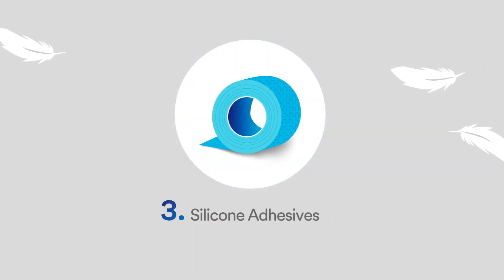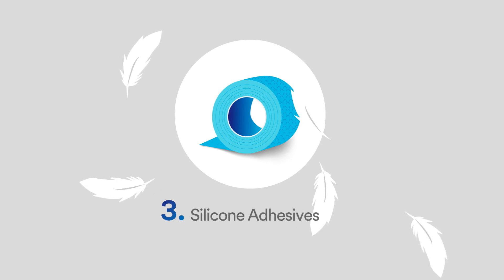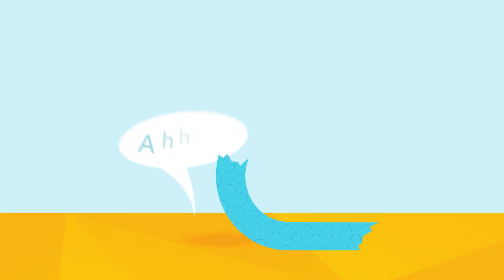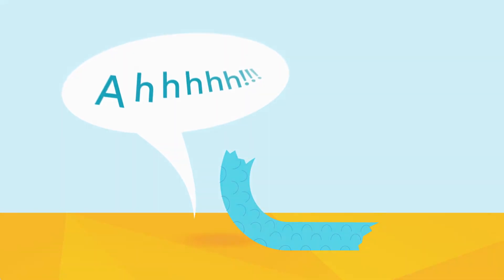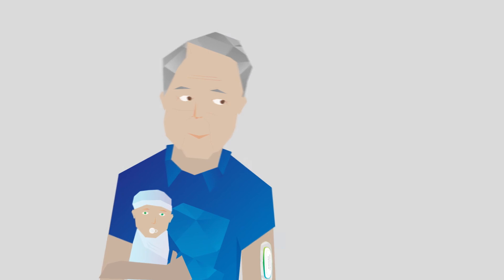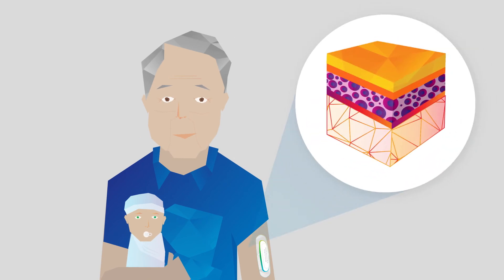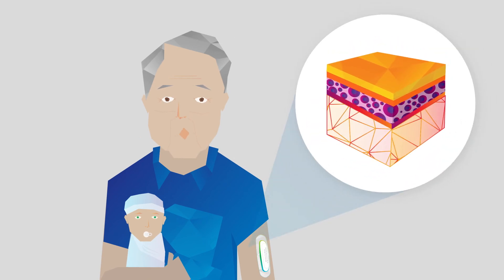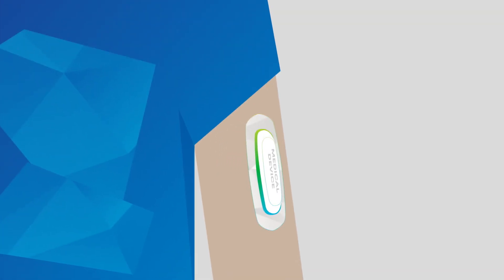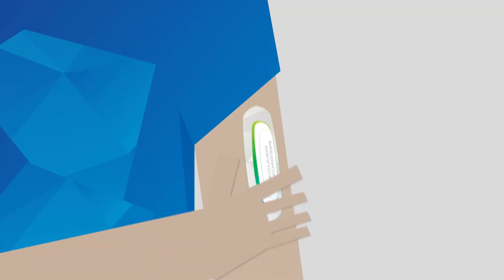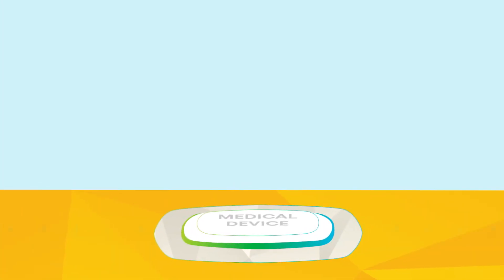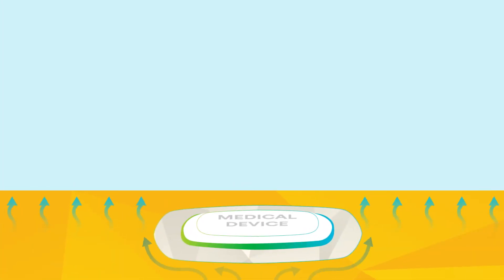Silicone PSAs are very gentle adhesives with low peel adhesion, so they typically result in less skin trauma when removed. They're a great choice for babies and elderly patients who have fragile skin. They're also an excellent choice for repeat applications to the same area of skin, or when you'll need to reposition the medical device, but they're used mostly for short-term applications.